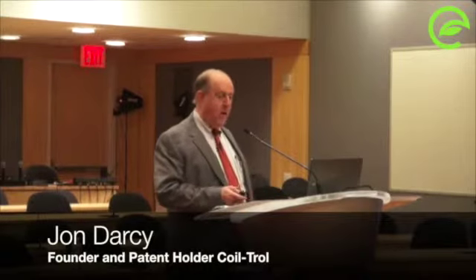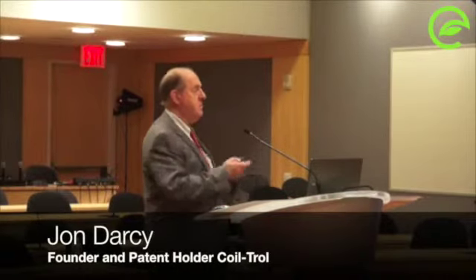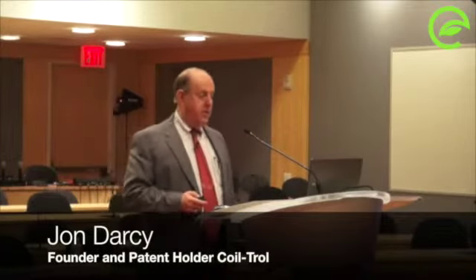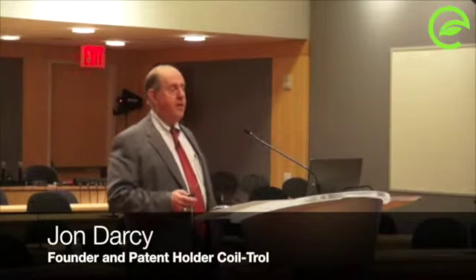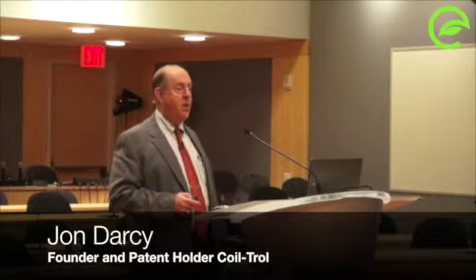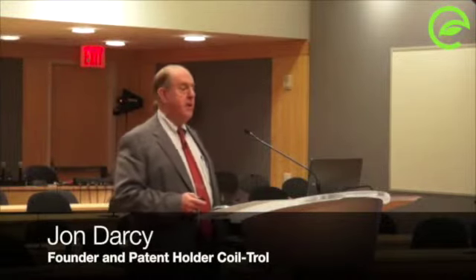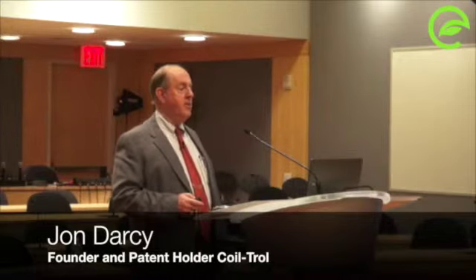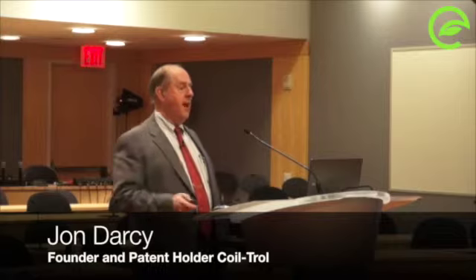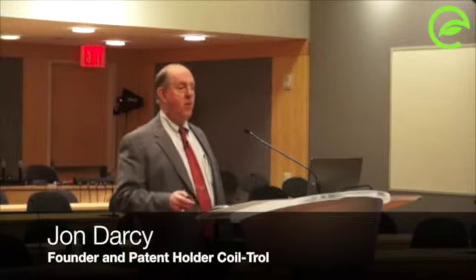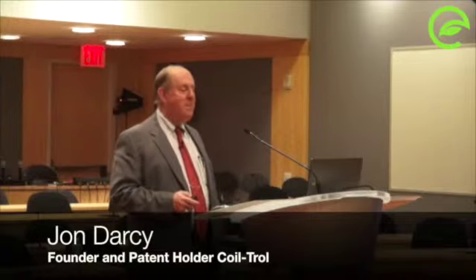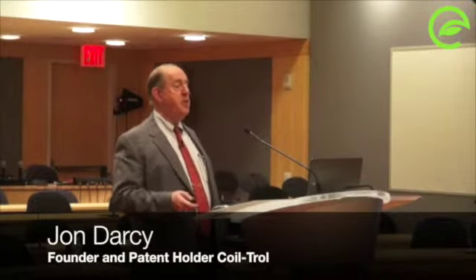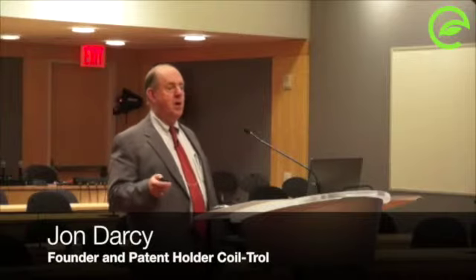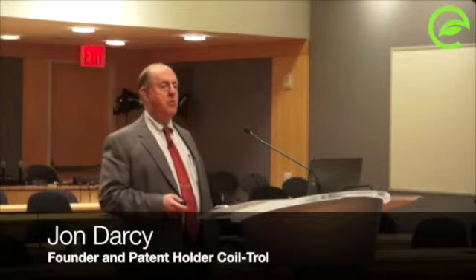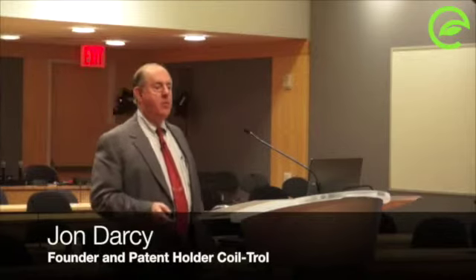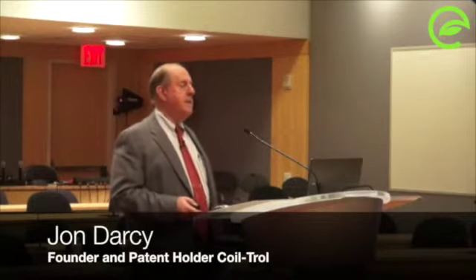So what I was looking to do, as I said, I was doing chill water control systems, and more than half of the high-rise office buildings in Manhattan at one time had my chiller controls on them. So I did a pretty good job of marketing that in New York. Subsequent to that, a lot of those chillers have been ripped out. Shows you how old I am. And a lot of the features that I had built into my Thermomizer chiller controls actually came with the new chillers, like PID control and chill water reset and some of that stuff.